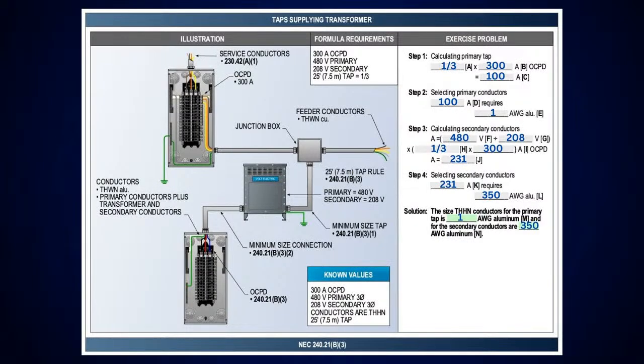Okay. So if I look at the primary, I've got a 300 amp overcurrent device upstream. I take it at a third, that's 100 amps. I go over to table 310.16, 75-degree C column, and need a number 1. Now, right here in step 3, when I'm doing that secondary, I have to get the ratio of the transformer. I have a 480 volt primary and a 208 volt secondary. So I'm going to divide that 208 volt into that 480 to get that ratio. Then I will take the amperage and a third of that, and that'll give me 231 amps.